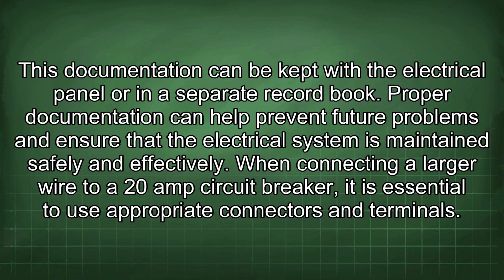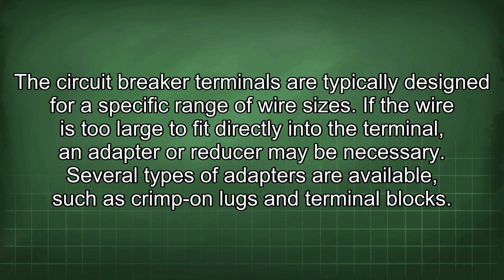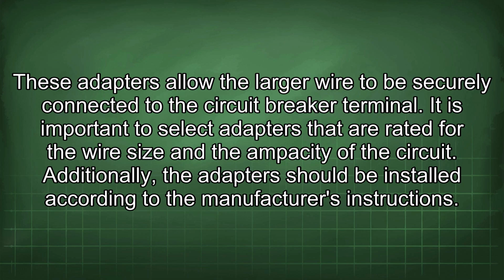When connecting a larger wire to a 20-amp circuit breaker, it is essential to use appropriate connectors and terminals. The circuit breaker terminals are typically designed for a specific range of wire sizes. If the wire is too large to fit directly into the terminal, an adapter or reducer may be necessary. Several types of adapters are available, such as crimp-on lugs and terminal blocks. These adapters allow the larger wire to be securely connected to the circuit breaker terminal. It is important to select adapters that are rated for the wire size and the ampacity of the circuit. Additionally, the adapters should be installed according to the manufacturer's instructions.